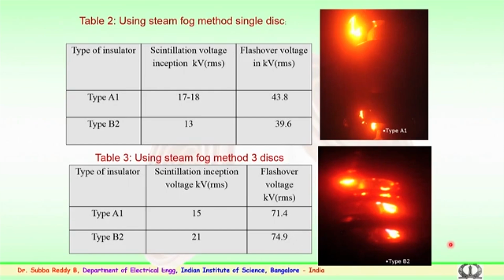So, these values, similarly for the insulator B2, you can see the scintillation starts around 21 kilovolts in case of 3 discs in a string with a larger creepage and diameter which I mentioned earlier, and the flashover is around 74.9 kV for 3 discs in a string.